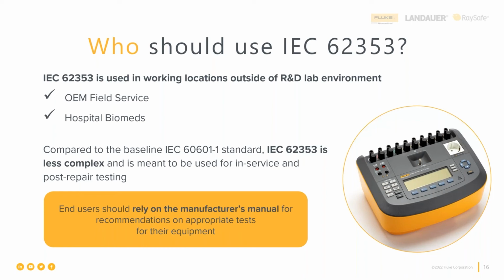and does not have tests in it that would tend to shorten the useful life of the medical device, which the IEC 60601-1 does have and needs to have, because why? This IEC 60601-1 is intended for design validation testing and factory final assembly testing.